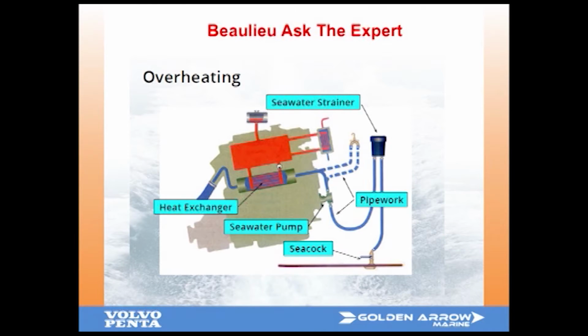What actually happens is, if you look at where the seawater pump is, it goes up to what we call the heat exchanger, and that's where most of those bits of the impeller will end up. So you need to take the end cover off the heat exchanger and take all the bits out. It's a bit like a jigsaw puzzle - try to make sure you've got all the bits there. Then hopefully you'll get the engine up and running again.